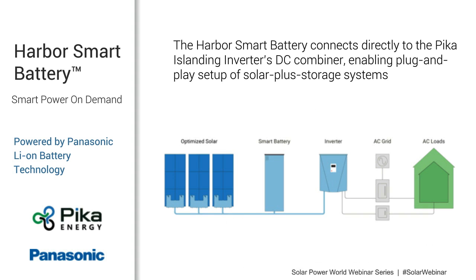This diagram kind of shows in further detail here. You have the optimized solar from our PV link on the left side. Your Harbor Smart battery connects in parallel on that same DC bus. There's a breaker assembly inside the inverter with 4 30-amp DC breakers, and you can put any combination of PV and battery on that breaker assembly. And I'll get into some more detail on that for different configuration options that are available.